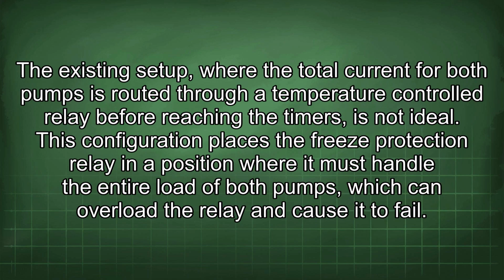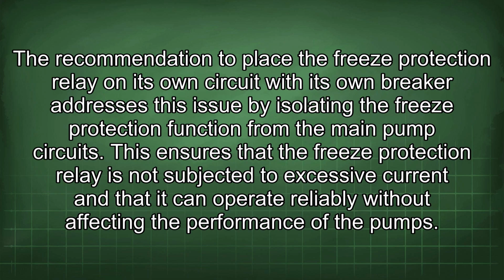The existing setup, where the total current for both pumps is routed through a temperature-controlled relay before reaching the timers, is not ideal. This configuration places the freeze protection relay in a position where it must handle the entire load of both pumps, which can overload the relay and cause it to fail. The recommendation to place the freeze protection relay on its own circuit with its own breaker addresses this issue by isolating the freeze protection function from the main pump circuits. This ensures that the freeze protection relay is not subjected to excessive current and that it can operate reliably without affecting the performance of the pumps.